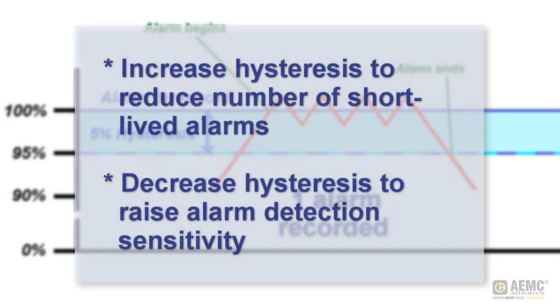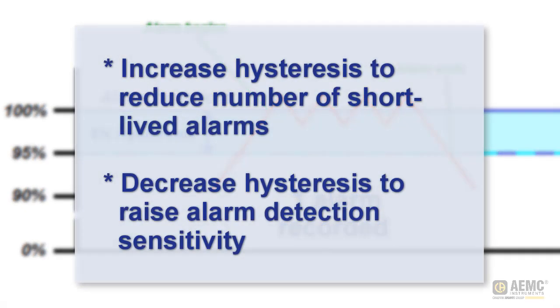By adjusting hysteresis, we can control the sensitivity of the alarm trigger. If your recording session results in a high number of alarms, you can set hysteresis higher. If the recording captures few alarms, you can lower the setting to ensure actual fast, short-lived events are not being missed.